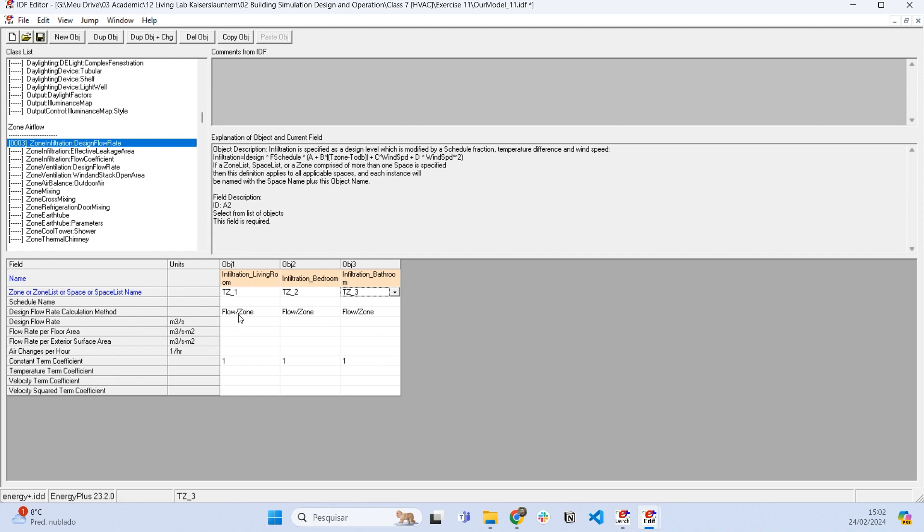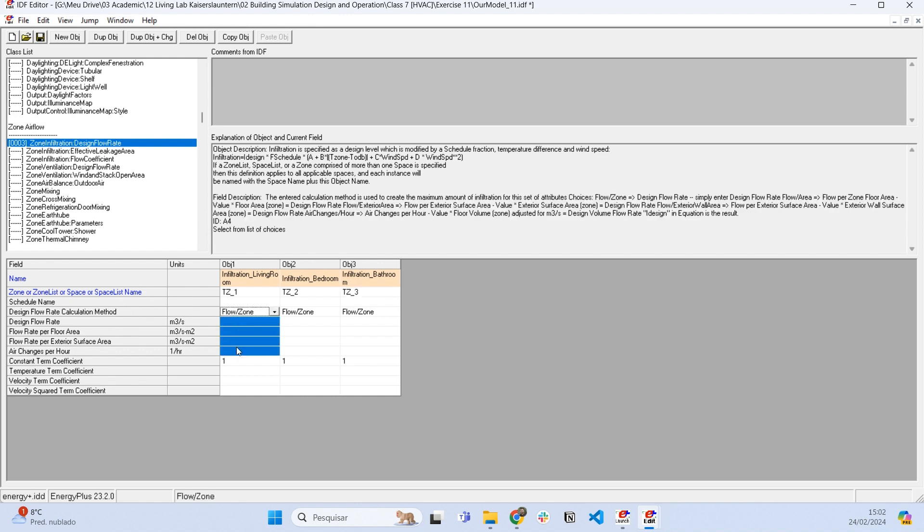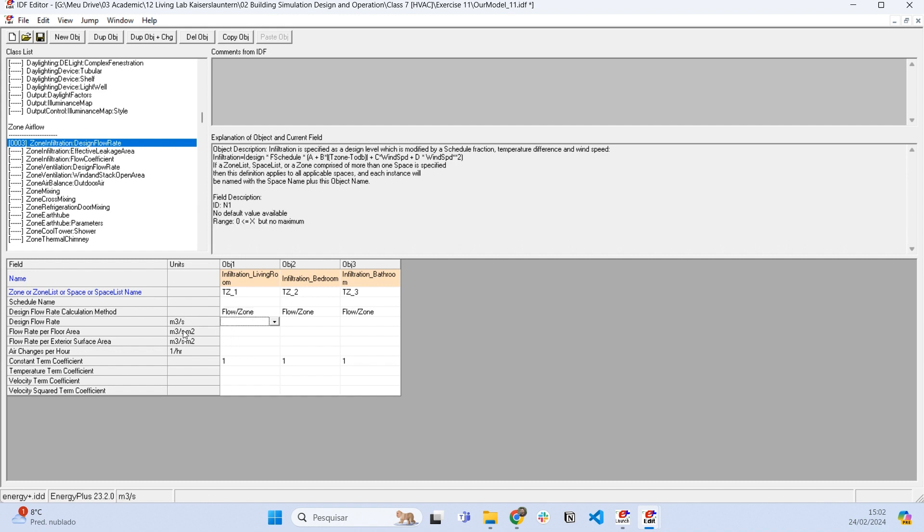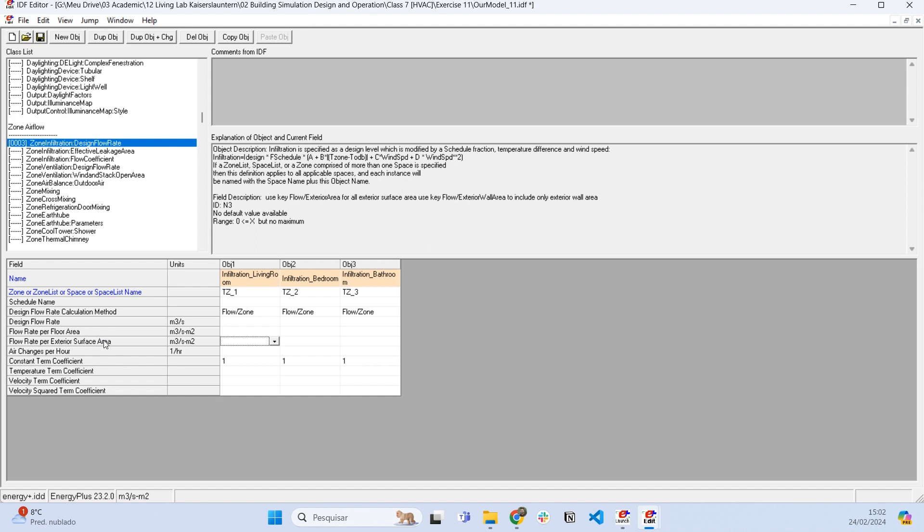It's very similar to the air renovation. We can set a method like design flow rate in cubic meters per second, flow rate per floor area, and flow rate per exterior surface area. This is very useful when we have measurements of the windows and the quality of the window, so we can set how much air flows through its cracks.